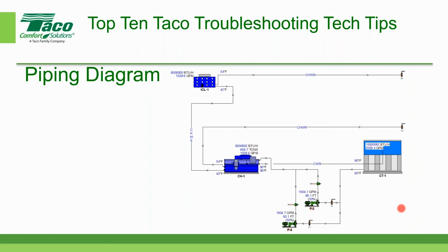Okay. So we have a little diagram. This is what they gave me initially, and it looks fairly straightforward. I can see that the diagram is telling me that the two pumps are piped in parallel. Each pump is roughly 1,000 gallons per minute at 80 feet. And the diagram indicates that there's really nothing between the cooling tower, in this case an open cell cooling tower, and the inlet to the pump other than an isolation valve. At least that's what the initial information is all about.